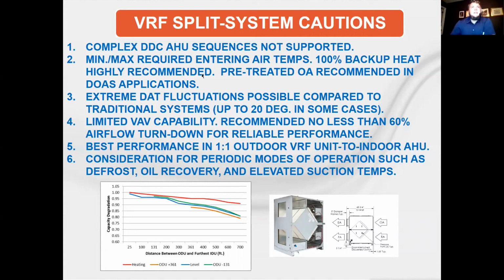Another big one for Chicago, just keep in mind, is the minimum and maximum required entering air temps. Now, these aren't just like the mins that we might tell you on a heat pump, that if you're giving it less than 35 degree entering air, it might freeze up. This is more like the VRF system is literally measuring the entering air going to the coil, and it's hard coded so that if it's below or above a certain temperature, it might not even let it cool or heat. So, there's some of the details to keep in mind.